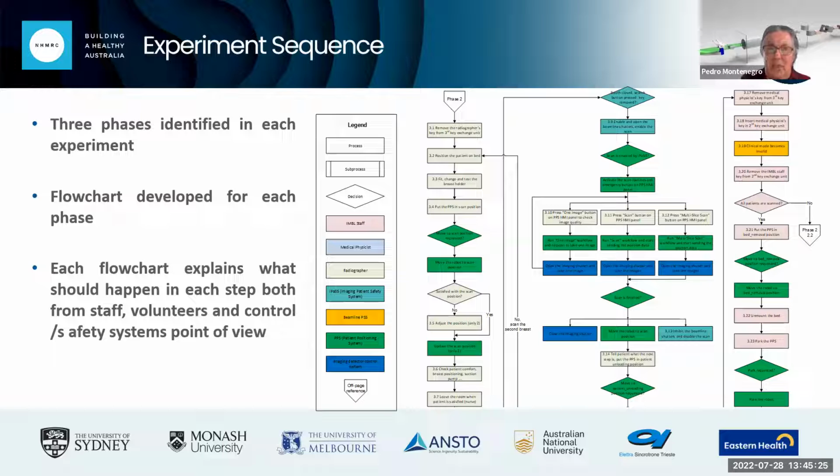Once we have done this, we fill in a handover sheet for the medical physicist where we say we've done all this, we have got that dose, and we put our key in the key cache, turn it, free the medical physicist key, and give the medical physicist their key. If they are happy with the report and the dose, they will activate their part of the flow chart and go through all those points. When they're ready, the medical physicist will have verified everything, and then they will be ready to hand over to the radiographer. This handover is also done through the key cache.